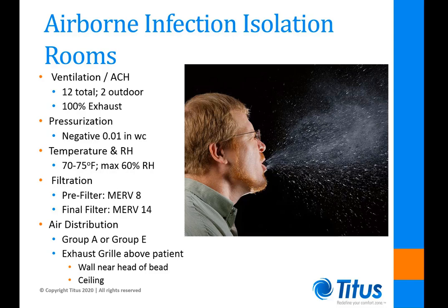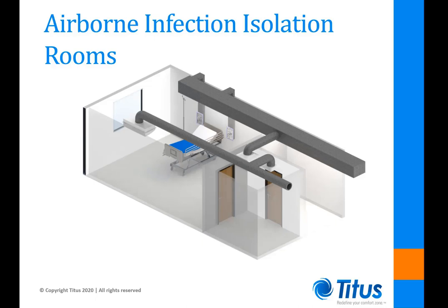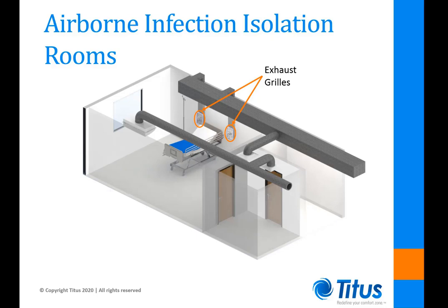Looking at a typical AII room layout, there is a one-way radial throw diffuser throwing towards the bed, located on the wall opposite the foot of the bed, directing airflow from the left side of the room over the patient towards two exhaust grills on the side wall. The grills can be placed on the side wall or ideally about a foot or two out from the wall in the ceiling. This non-aspirating, radial throw diffuser pushes into the room, displaces the air around it, and creates a path for air flow over the patient and up to be exhausted and removed from the space.